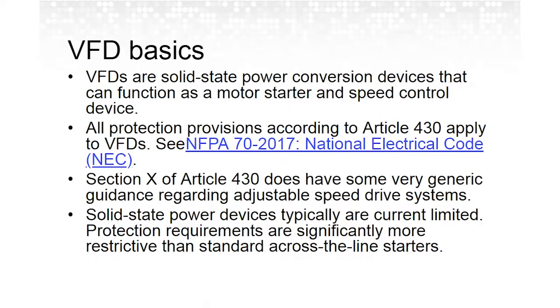If the fan goes slower, there's less cooling air, so you have issues dissipating heat from their internal windings. So there are guidelines within the article, well, not very specific, that basically state that you have to have some level of overheating protection for that motor. In the same breath, it doesn't really state a heck of a lot about the VFD itself.